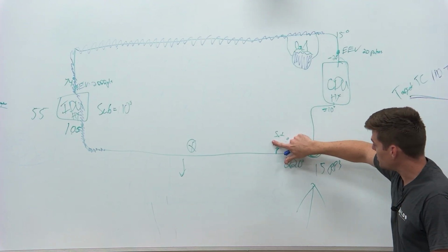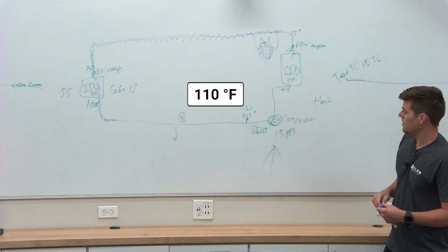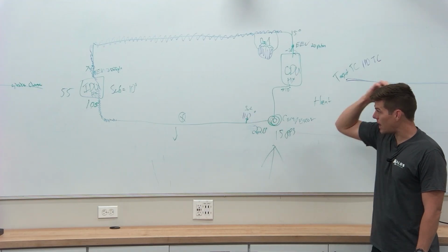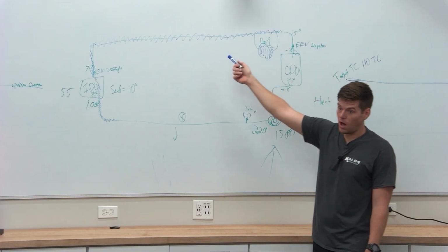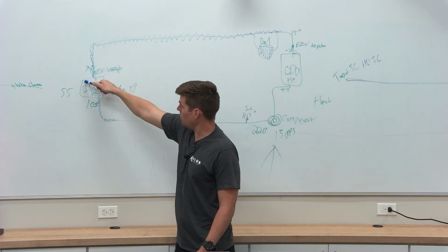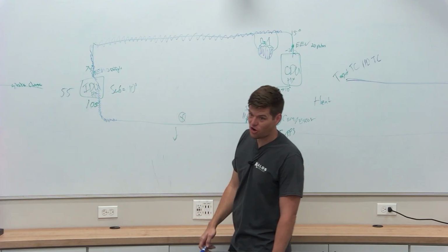And so my saturation temperature hasn't changed. Well, it has because we gave it a target of 110. It's 110. This isn't going any faster. This hasn't changed. So what starts to happen? It starts to stack liquid on one side of the system. And that liquid stacks so much that it starts to fill the indoor unit. Then it comes down the actual gas discharge line.